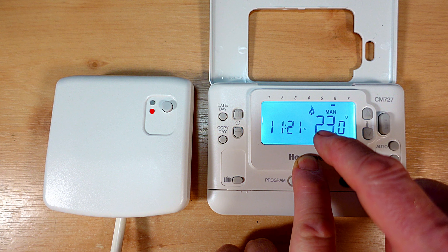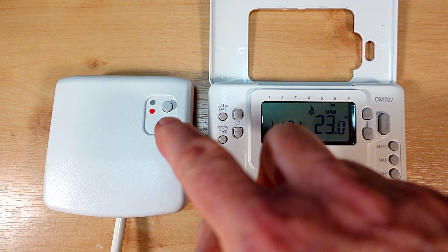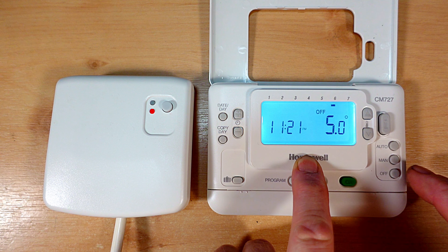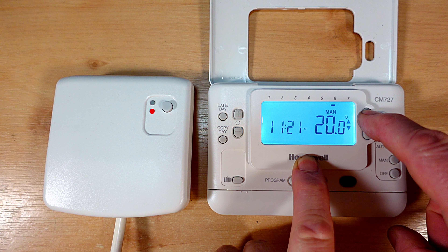You should also see the radio symbol flashing to indicate that it's sending the signal to the receiver unit. We should then see the green light come on on the receiver unit. If the green light doesn't come on then it probably means that we have lost the binding between the two units or that one of them is faulty. You could just repeat turning the heating on and off to make sure that they are talking to each other.